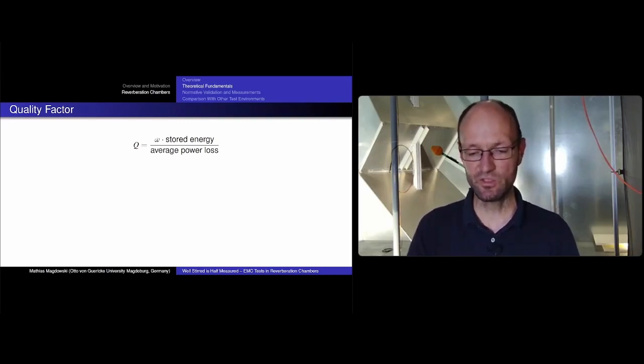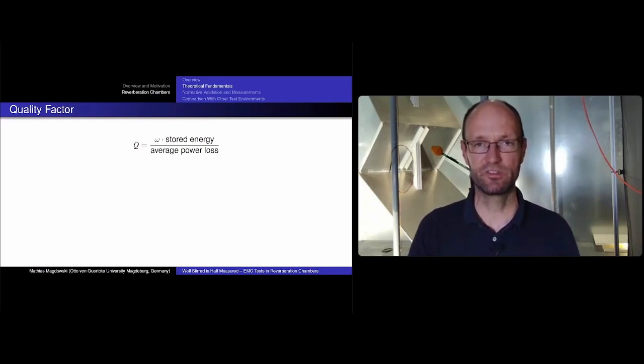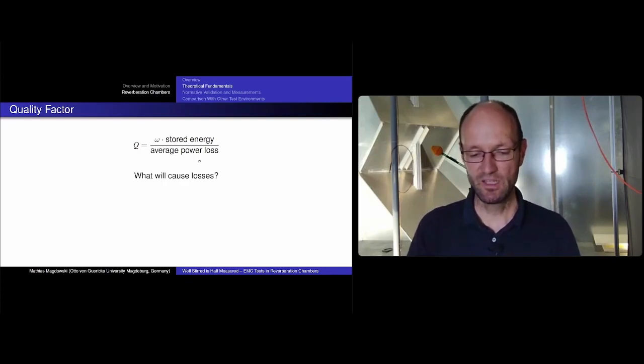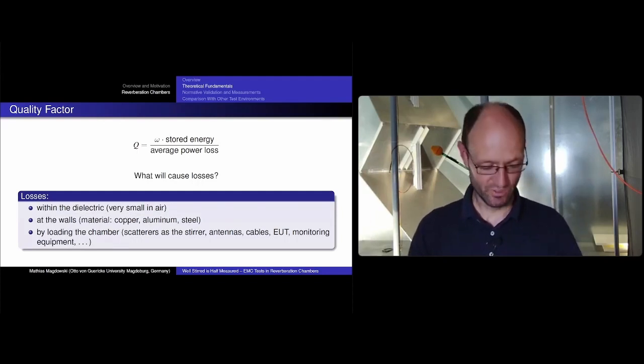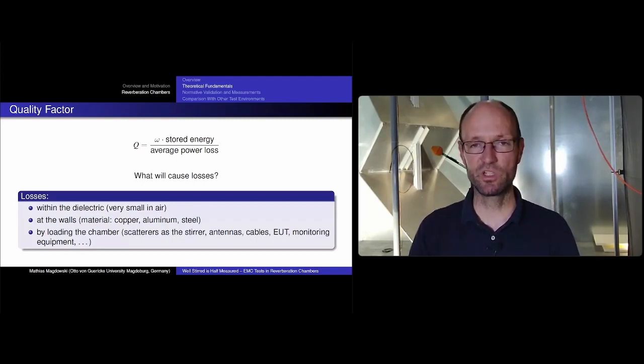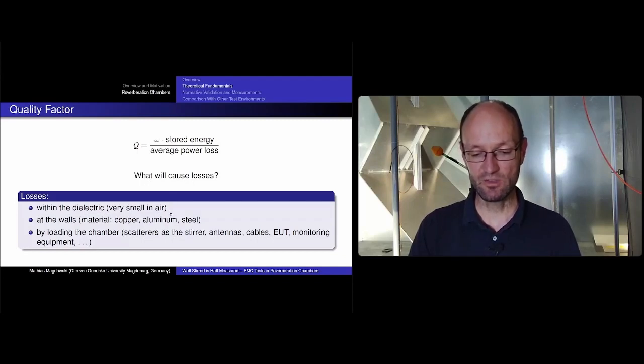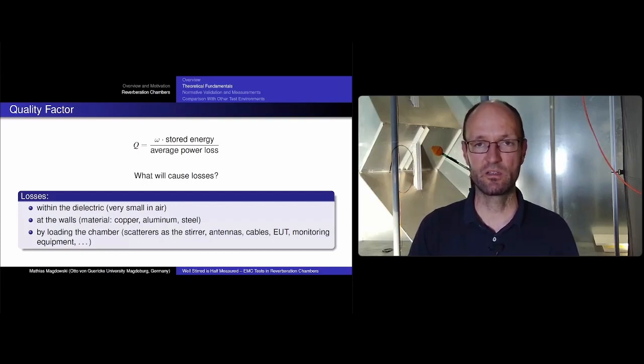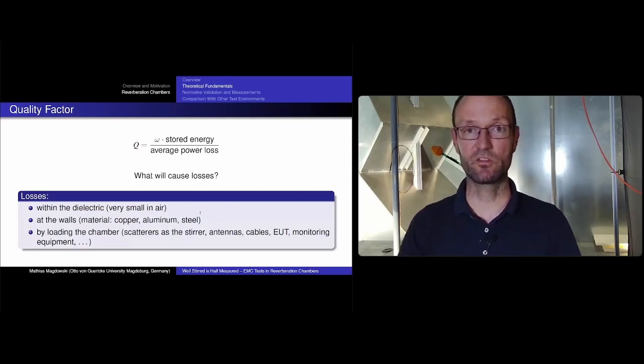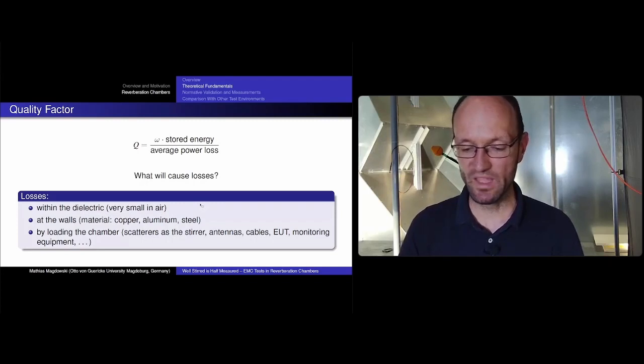The quality factor Q is the angular frequency multiplied by the stored energy, divided by the average power loss per cycle. Losses come from the dielectric inside — usually air, so very small — from the walls made of steel, copper, or aluminum, and from anything placed inside including antennas, cables, and the EUT. At low frequencies, the highest losses often come from the antennas because they have a large effective area at long wavelengths.